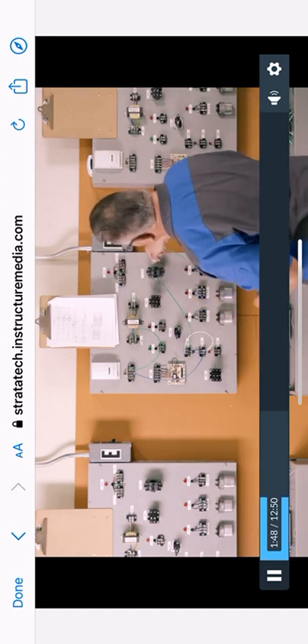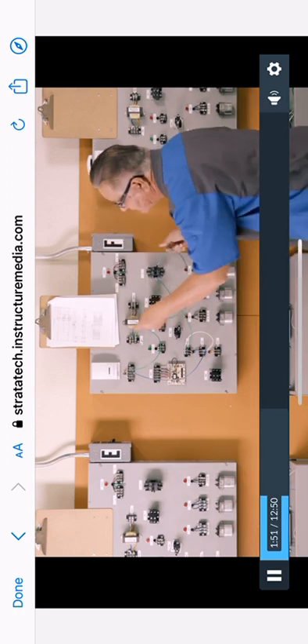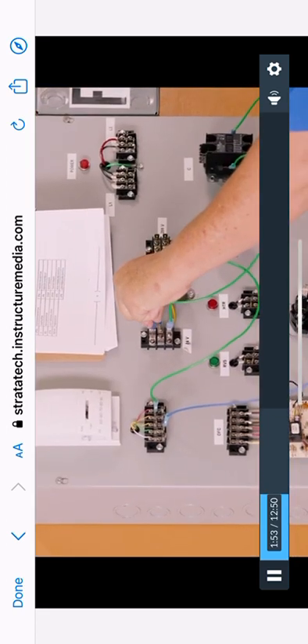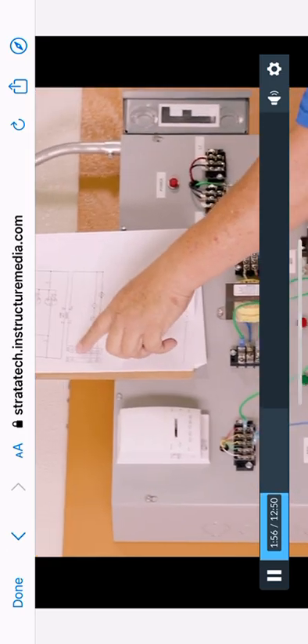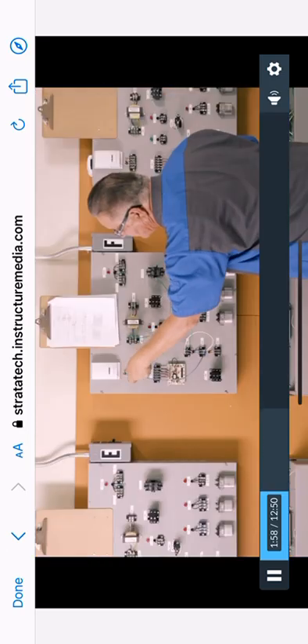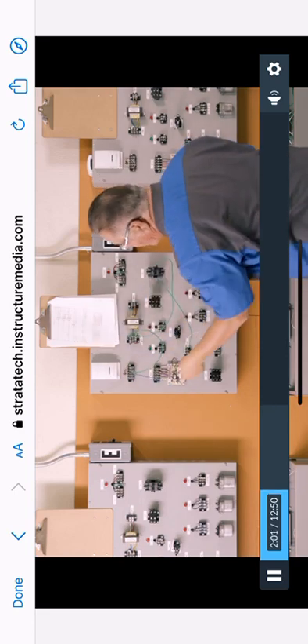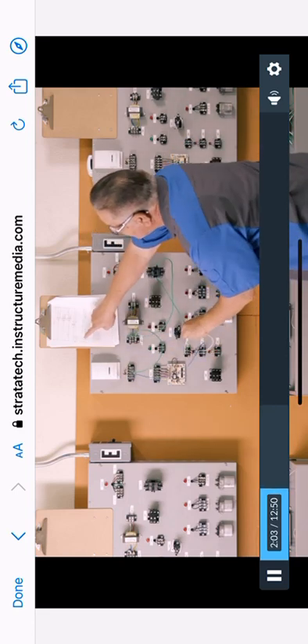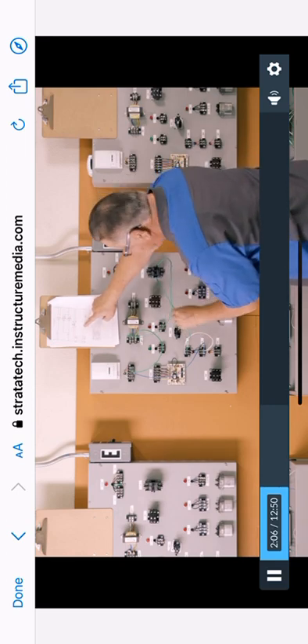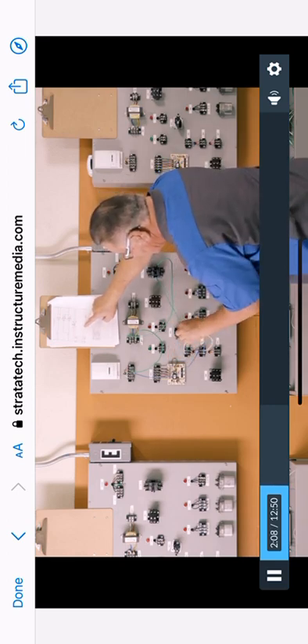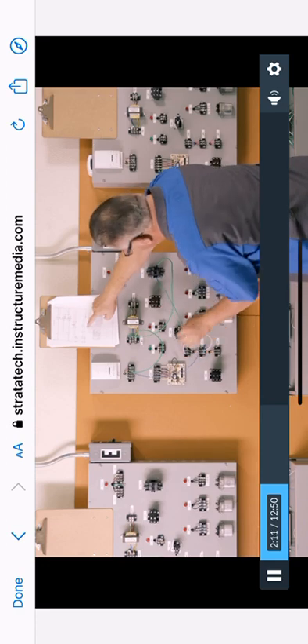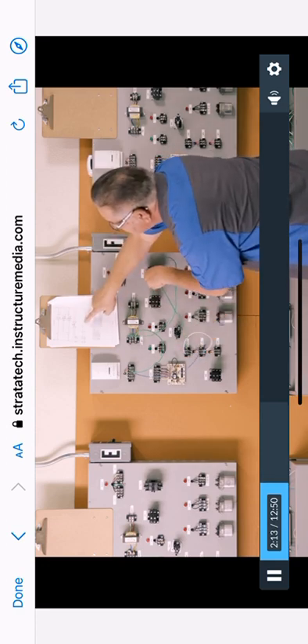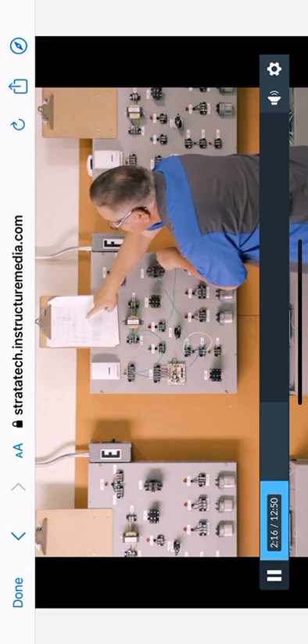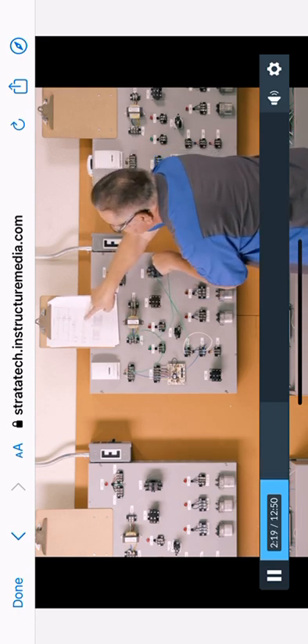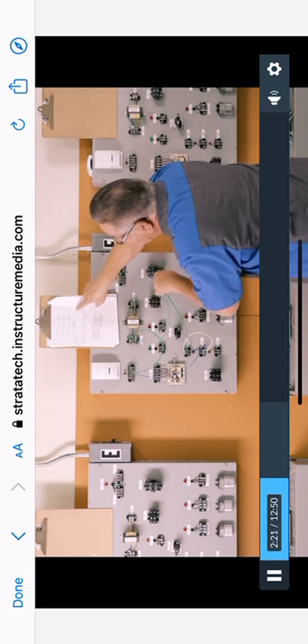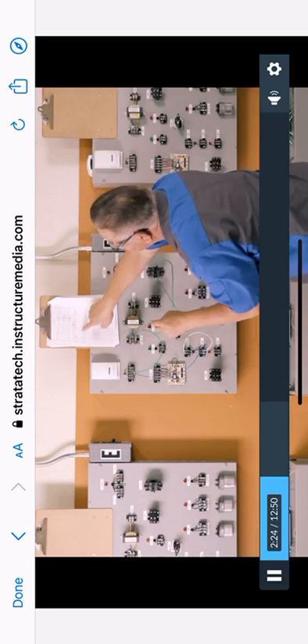Here we go. So I'm going to go to the other side of the contactor coil and I'm going to go to my common, which is this blue wire up here. I just completed my R, 24 volt to my thermostat right here. I just ran my Y to my low pressure switch, came out of my low pressure switch, went to my high pressure switch right here at this white wire, came out of my high pressure switch, this green wire, went to one side of my contactor, completed that circuit. Now I came out of my contactor coil, sorry, and I went back to my common, which is right there. So I just completed that circuit.